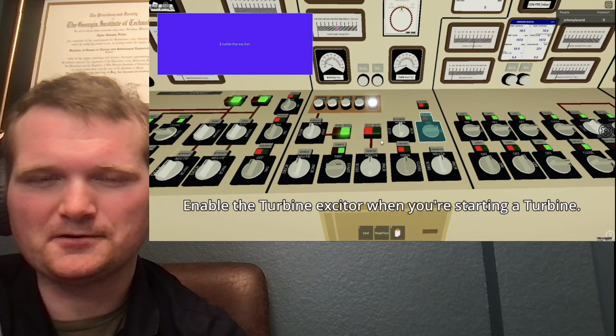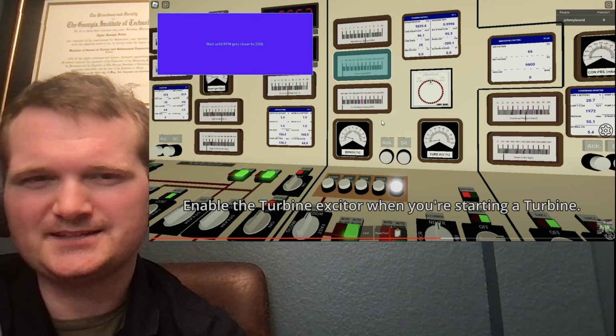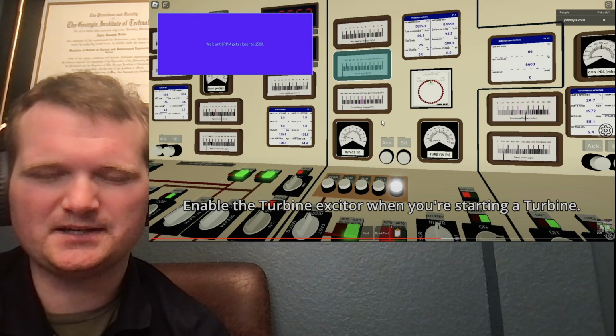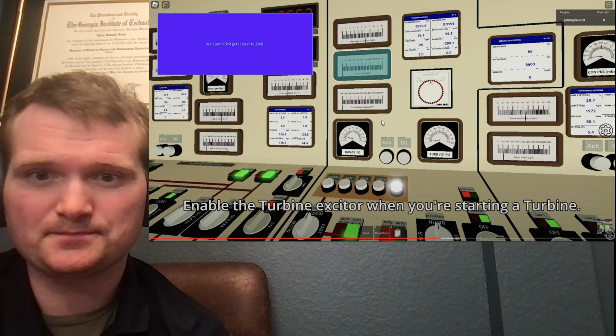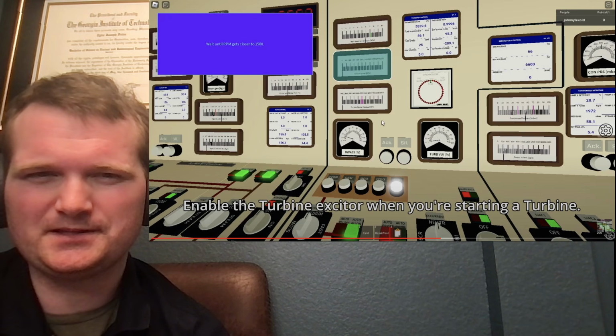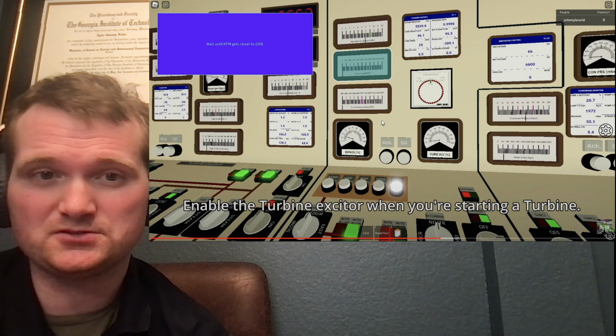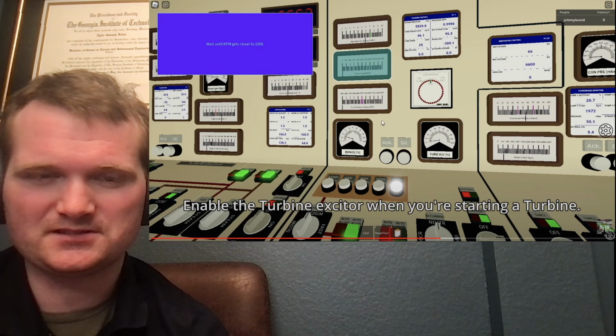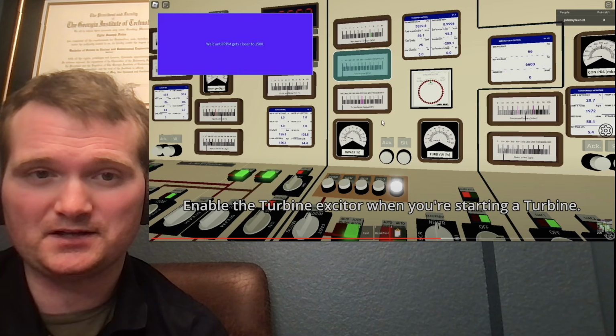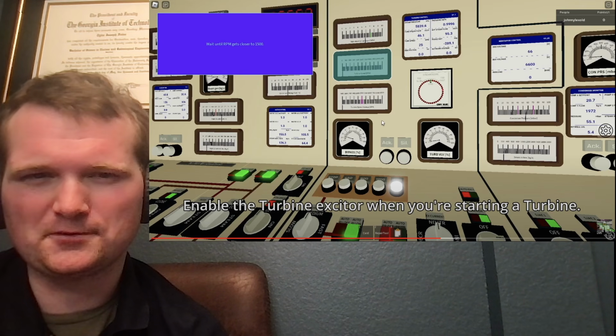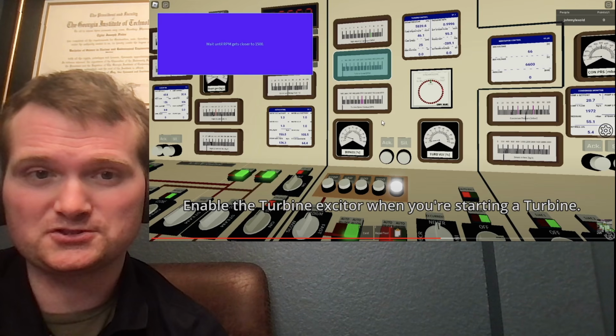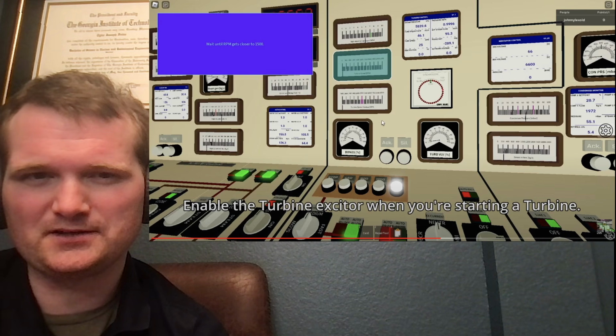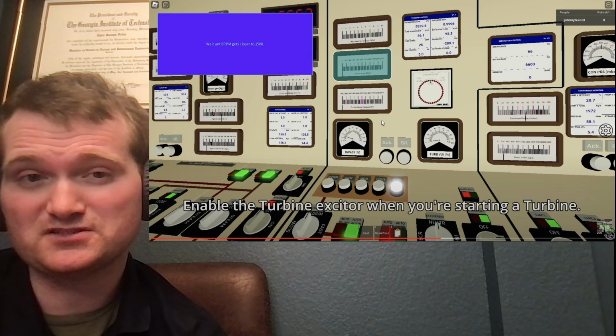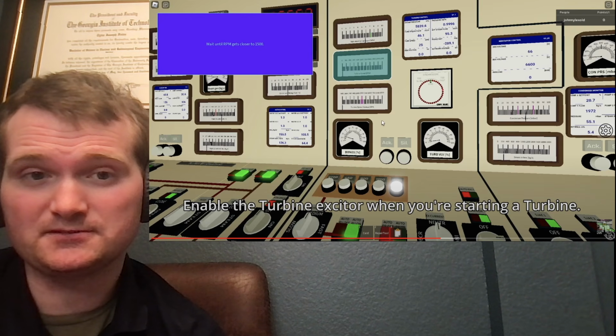Now they're going to start the turbine, all right? Enable the turbine exciter. It's actually for the generator. Now what an exciter does is it generates magnetic fields to induce voltage in the generator. It typically uses a very small portion of the generator's output, converts it into direct current, and sends it to the generator's rotor to create a magnetic field, because the rotor is the part that spins. And that interacts with the stator, the part that doesn't spin, to create alternating current, which is the generator's main output that eventually goes to your house. So the exciter excites it by generating a magnetic field.